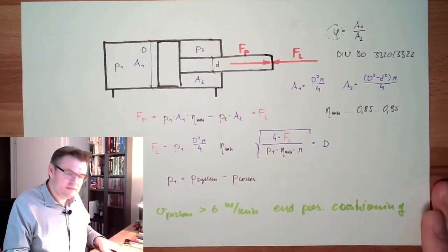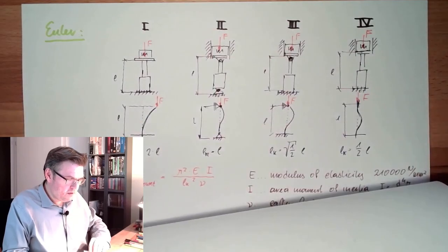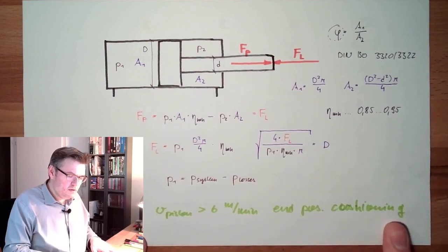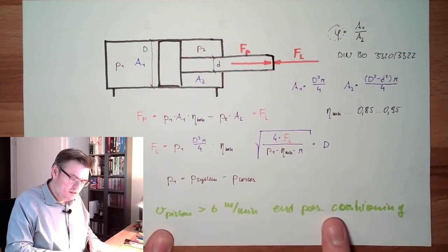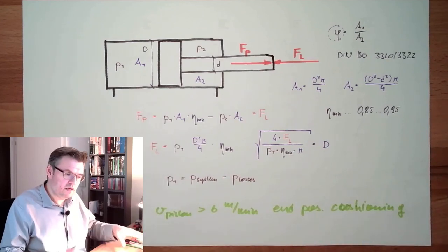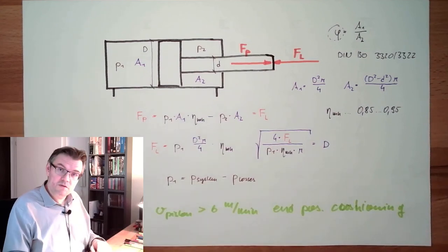This is how you select a cylinder: calculate the force, calculate the bending, determine the diameters, calculate the movement time, check if you need cushioning due to excessive velocity. Then you can already determine how many liters per second the pump must deliver for this cylinder. If you want to move more than one cylinder it will be double, triple, whatever. Next time we'll briefly talk about pump selection in a separate video, and after that we select the tank. Thank you very much for listening — goodbye, see you next time.